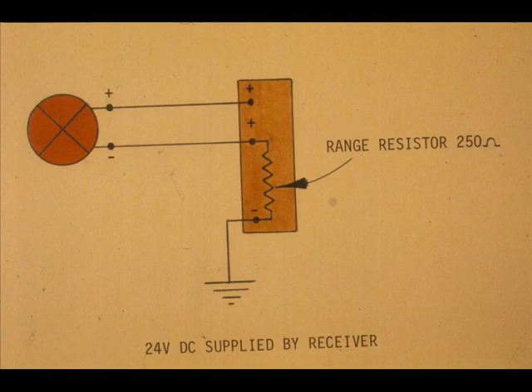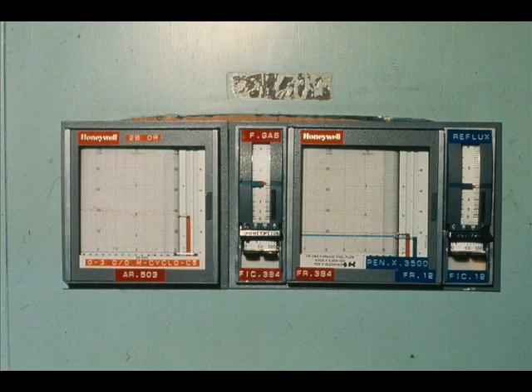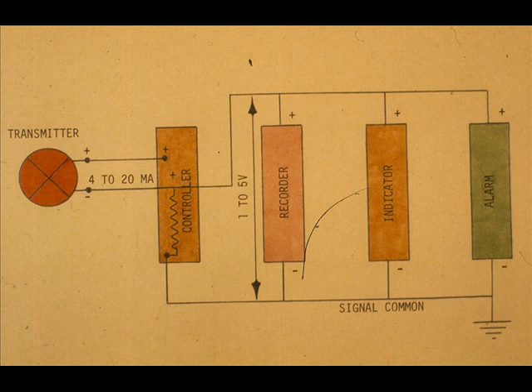The transmitter is connected in series with a resistor with one receiver only in the instrument loop. Since Honeywell receivers require a 1 to 5 volt DC signal, the range resistor is 250 ohms for the 4 to 20 milliamp DC transmitter.